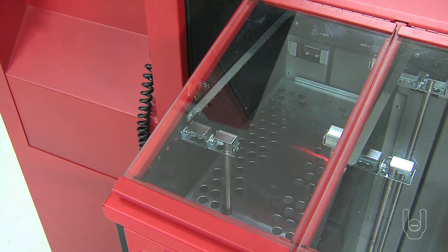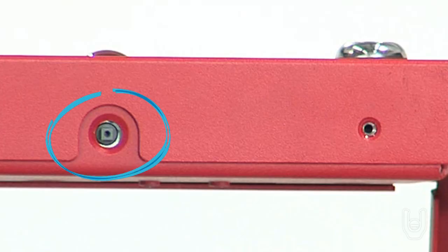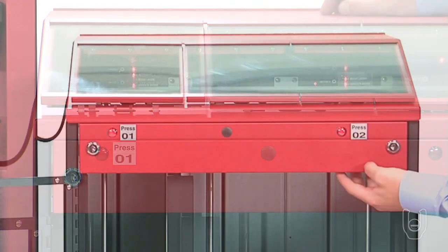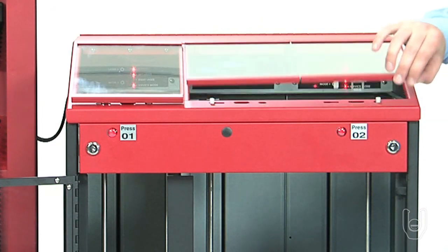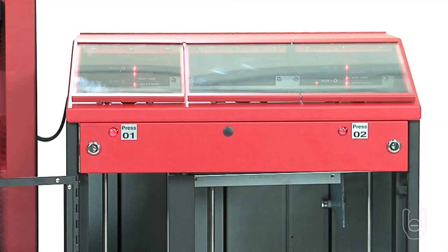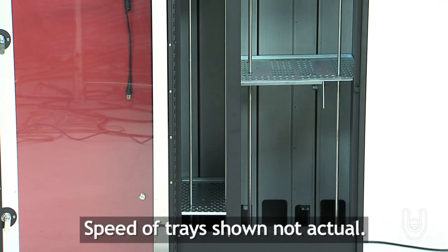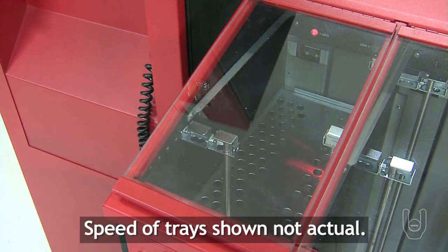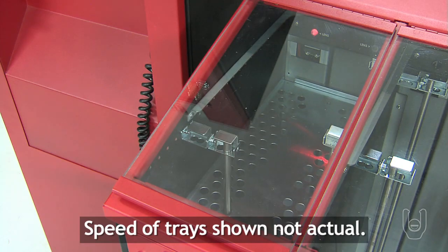If you wish to stop the lifter during the test cycle, you can simply press the bin door release button. The lifter is interlocked, meaning it will not move if the bin door is unlatched or open. When the bin door is closed, the lifter will restart the test cycle, moving the lift upwards to the upper limit. The test cycle always moves the lifter up first.